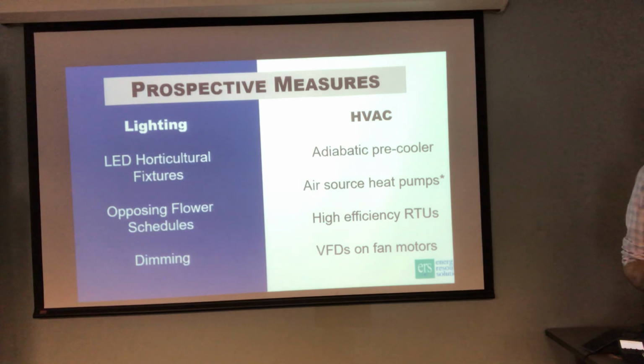This sprays a fine mist of water into the incoming airstream into the condenser. It results in wet bulb suppression, which makes the HVAC system not have to work as hard to reject the heat pulled out of your space. So it reduces demand on your HVAC system and adds some capacity. There are great incentives available for this, and it's not a very expensive installation to retrofit.